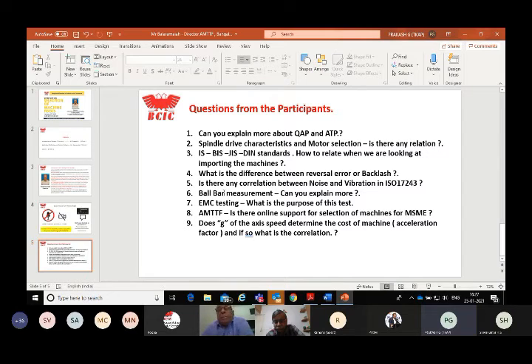Next is EMC. EMC is electromagnetic compatibility testing for the machine tool, to see how electrical discharge from the electrical elements on the machine is affecting things. There are electrical standards for that - radiation effect on the machine and conducted emission radiation. Normally this is done if you are exporting any machine tool, it's a must, part of CE testing. But nowadays in the local Indian market, people are not asking for that. Slowly it will become compulsory in coming days.